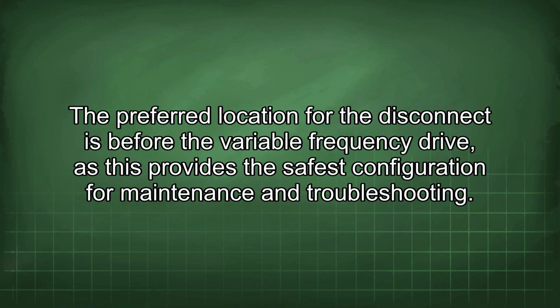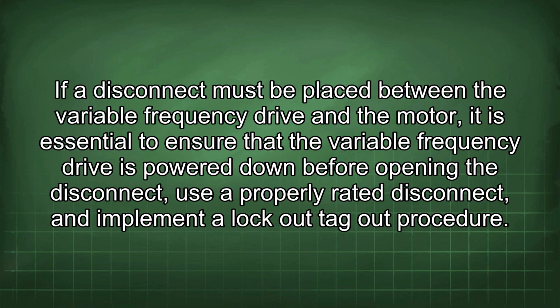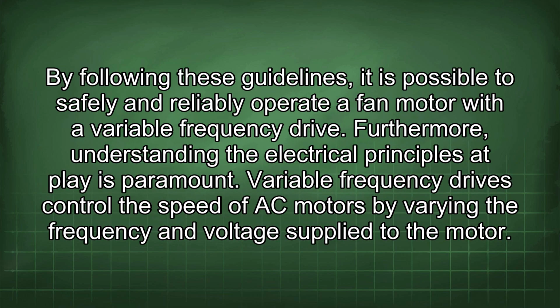The preferred location for the disconnect is before the variable frequency drive, as this provides the safest configuration for maintenance and troubleshooting. If a disconnect must be placed between the variable frequency drive and the motor, it is essential to ensure that the variable frequency drive is powered down before opening the disconnect, use a properly rated disconnect, and implement a lockout-tagout procedure. By following these guidelines, it is possible to safely and reliably operate a fan motor with a variable frequency drive. Furthermore, understanding the electrical principles at play is paramount.